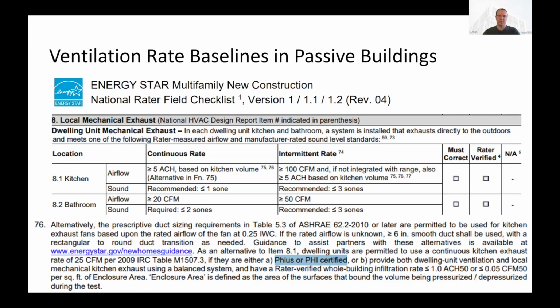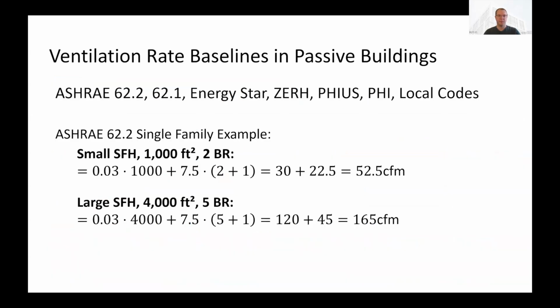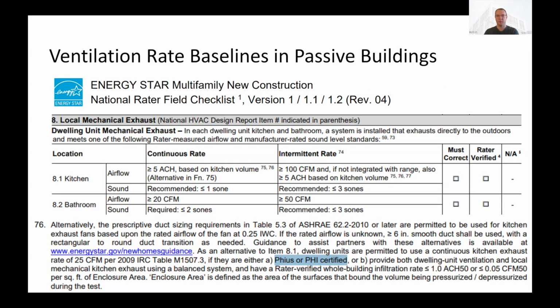So that large multifamily decentralized building we just looked at, those are kitchenettes or pretty small kitchens. And still, based on 5 ACH, we're looking at roughly maybe 60 CFM required for that kitchen exhaust. And it's worth referring back to the previous slide that that is the entire ventilation rate required by ASHRAE 62.2 on a continuous basis, just based on the local exhaust requirements. So there are other ways of dealing with that, but for now, we're just going to make an assumption that that's going to be a lot of airflow.